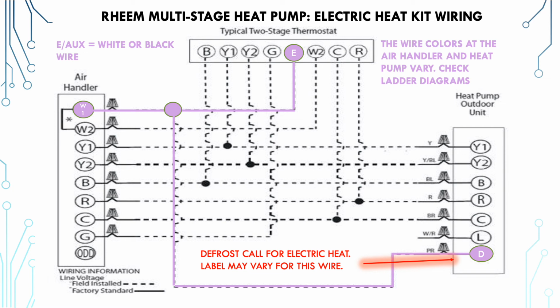With single stage, it's going to have a wire at the air handler that your thermostat wire coming off of the E is going to wire nut into. And then there's going to be a wire coming from the heat pump that you're going to also put in the same wire nut. They all just join together.